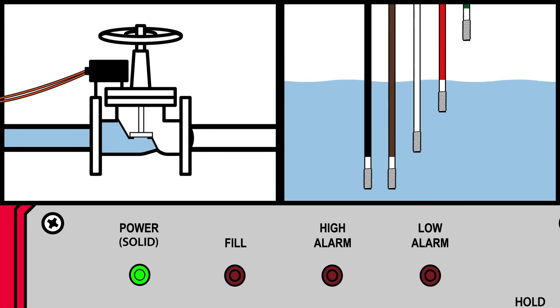Operationally, the valve opens when water drops below the white rod, and the LED for fill turns on, along with the respective relay and dry contact. The valve closes when the water reaches the red sensor rod.